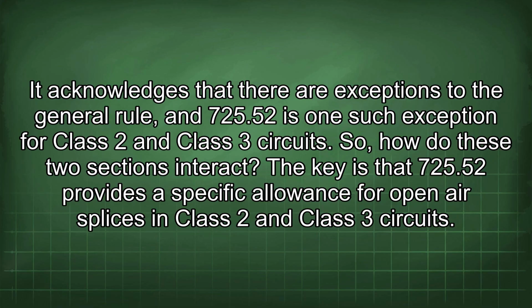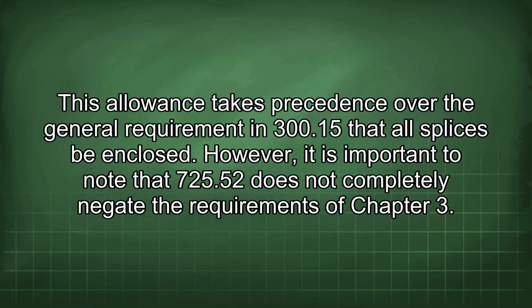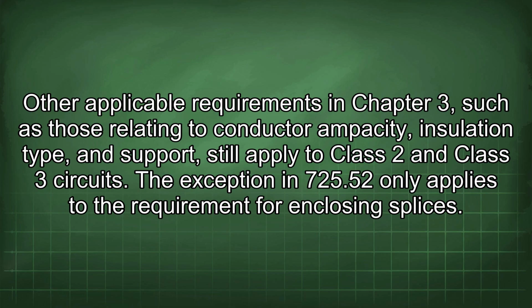So, how do these two sections interact? The key is that 725.52 provides a specific allowance for open-air splices in Class 2 and Class 3 circuits. This allowance takes precedence over the general requirement in 300.15 that all splices be enclosed. However, it is important to note that 725.52 does not completely negate the requirements of Chapter 3. Other applicable requirements in Chapter 3, such as those relating to conductor ampacity, insulation type, and support, still apply to Class 2 and Class 3 circuits. The exception in 725.52 only applies to the requirement for enclosing splices.